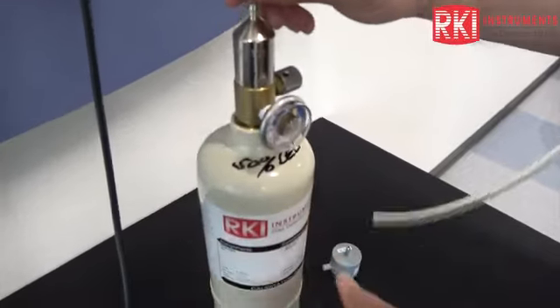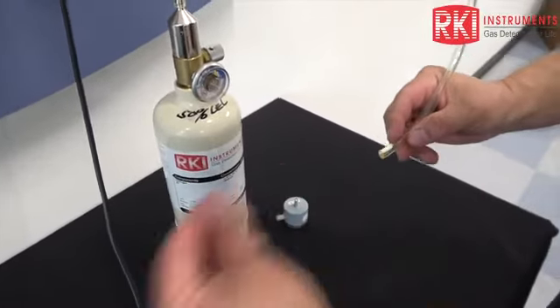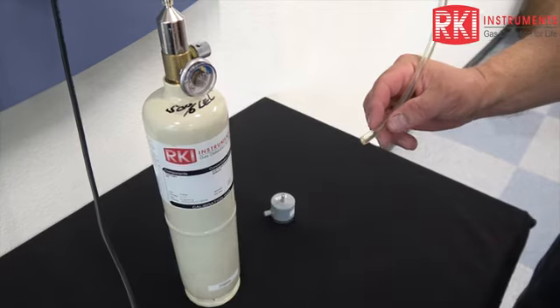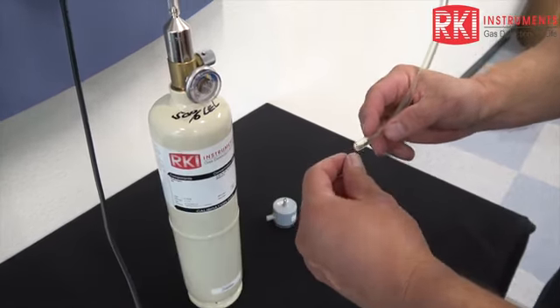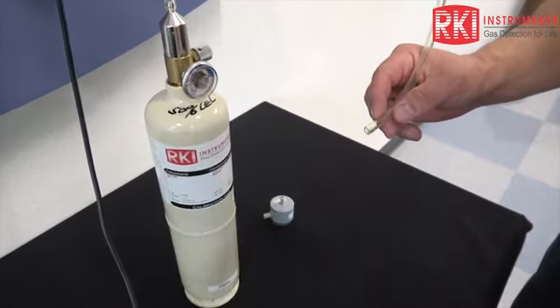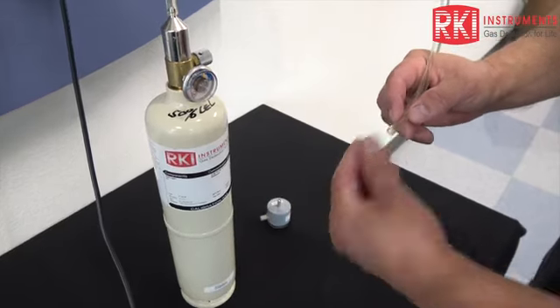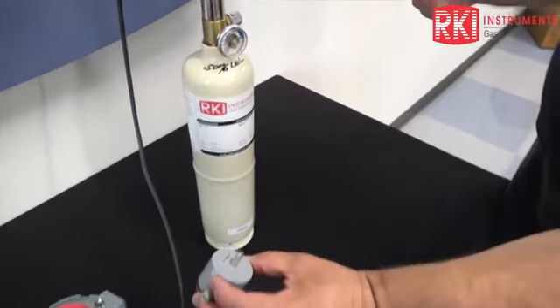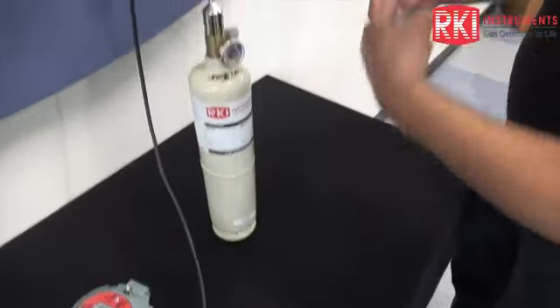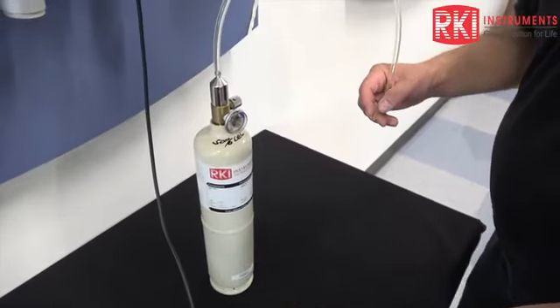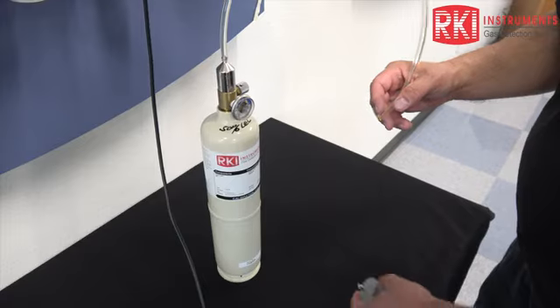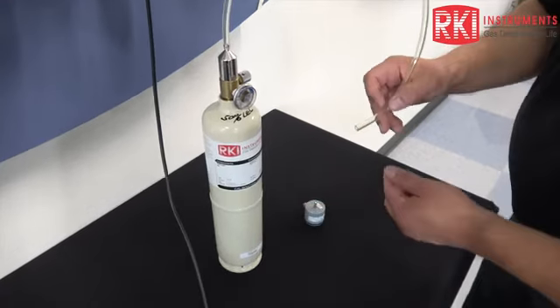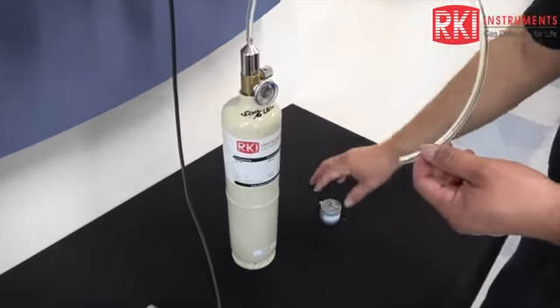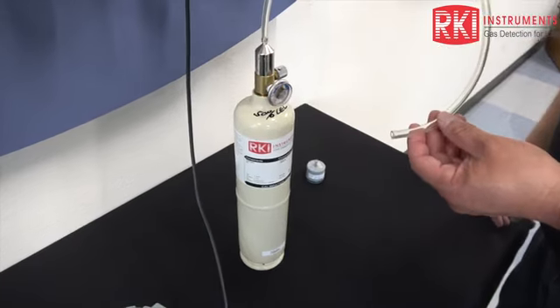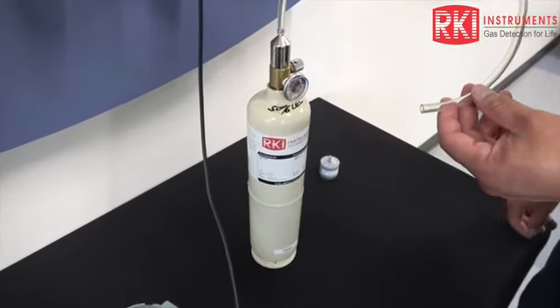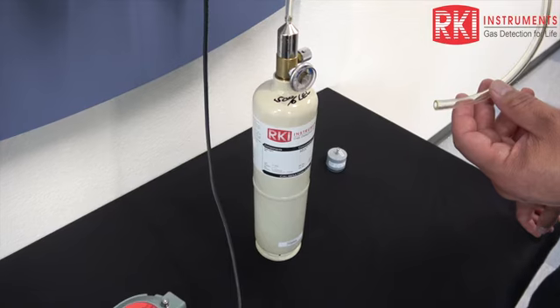And if this were benzene, then I would connect my section of that permeable tube, or the humidifier tube, and I would put one end here and then the other end on this cal cup. So then I want my gas sample going through the membrane just before entering into the unit. Okay, so that's how basically you would do a ppm range for hydrocarbons, or in benzene if that's what you're interested in detecting primarily.